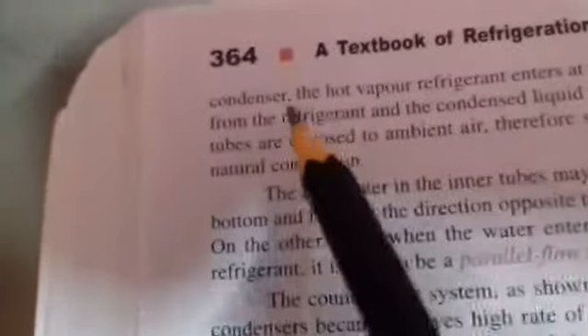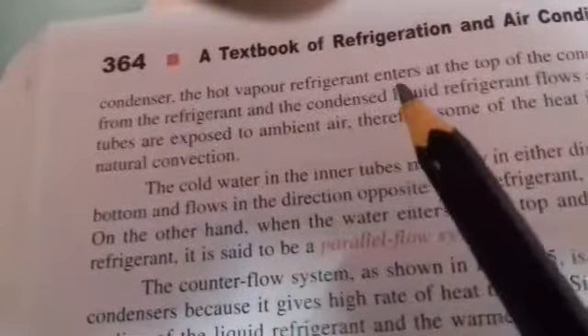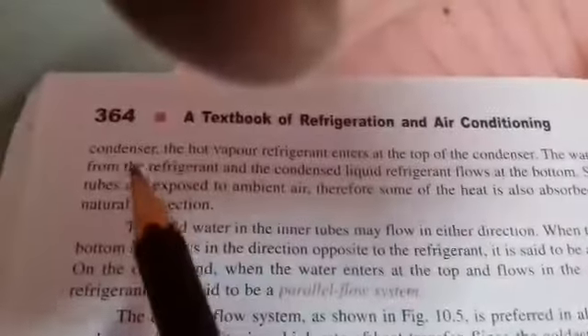In this type of condenser, the hot vapor refrigerant enters at the top of the condenser. The water absorbs the heat from the refrigerant, and condensed liquid refrigerant flows at the bottom. Since the refrigerant tube are exposed to ambient air, therefore some of the heat is also absorbed by the ambient air by natural convection. So this was your first one.